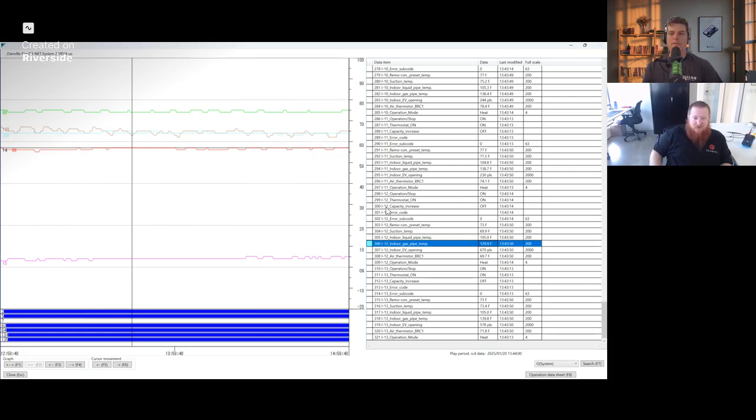Yep. And so to that point too, before we wrap it up, take this one home for the day, because it's a lot of information and we don't want to overwhelm you too much with this one podcast. Large changes where there shouldn't be is a huge red flag. If your discharge pipe temp is 224 degrees and your indoor unit is getting 130 degree hot gas, that is a huge temperature fall.